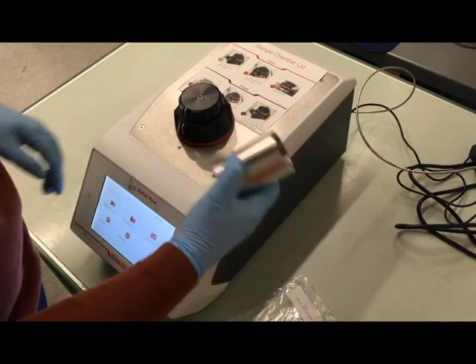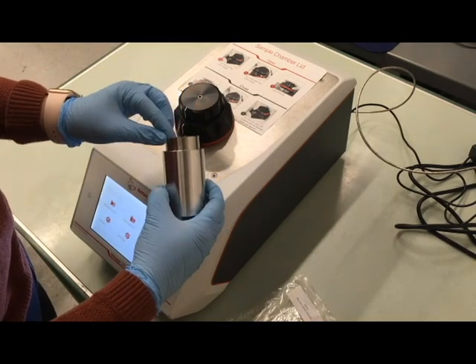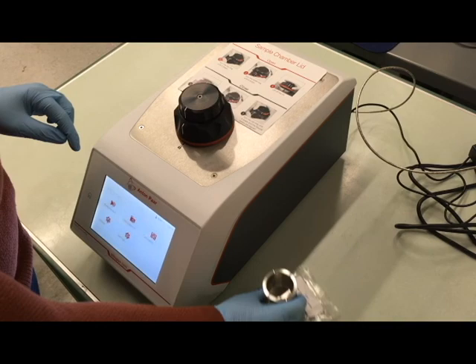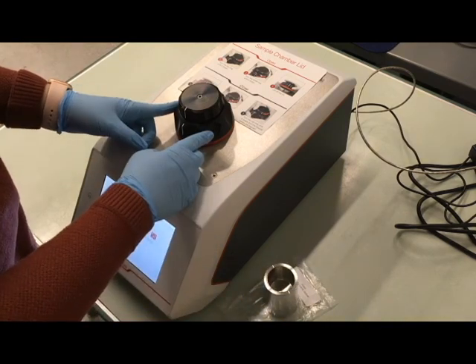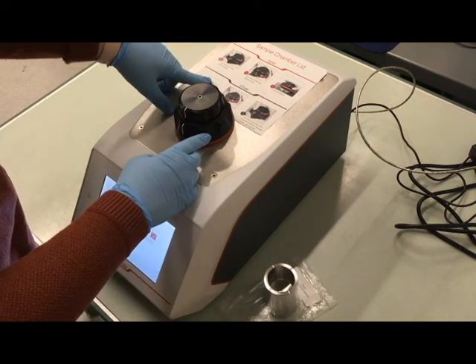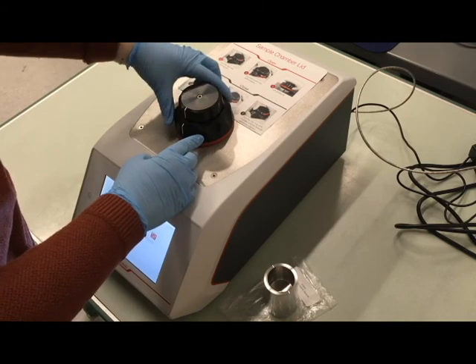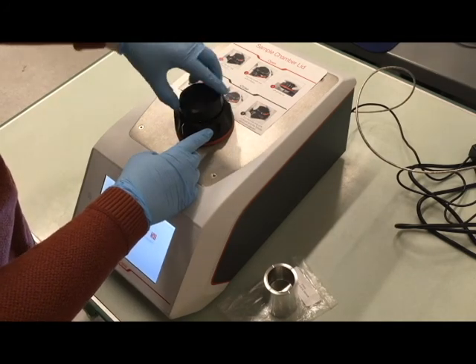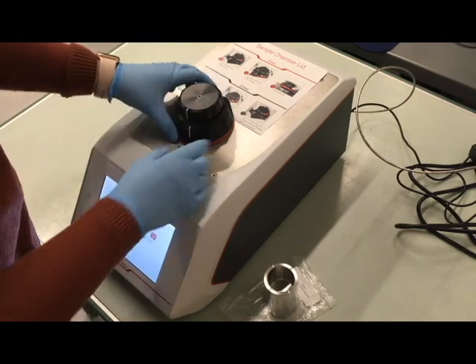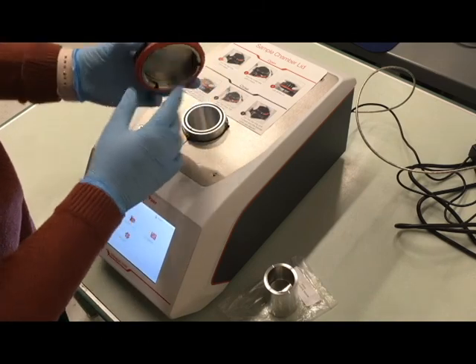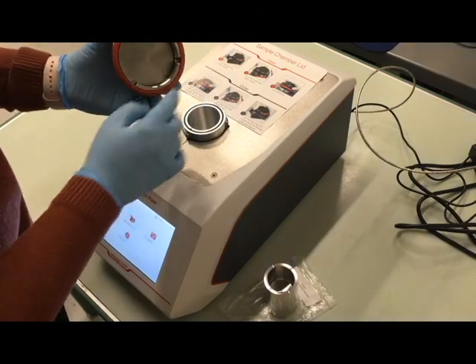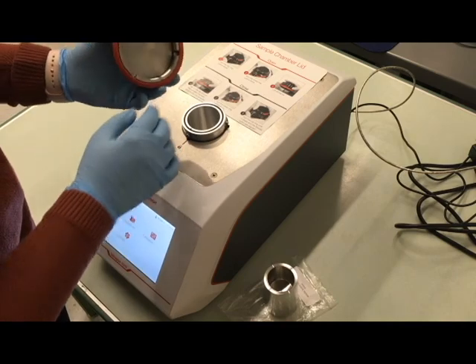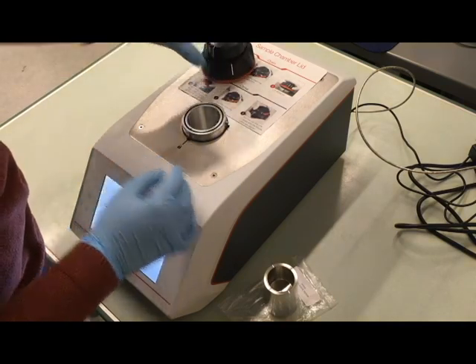To put the correct adapter and sleeve into the machine, pull out the corresponding bag from the drawer and pull off the lid. Instructions to take off the lid can be found on the top of the machine. We're going to loosen the top and then loosen the bottom and then lift this straight off. Please make sure that you set this on a nice clean surface so that we don't get any dust or dirt on the bottom of our lid.